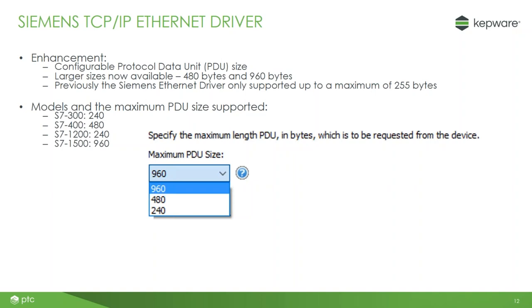For example, if I pick 960 and I was using an S7-400 that only supported up to 480, that will enable me to allow the protocol with KEPServer to negotiate it down to 480.